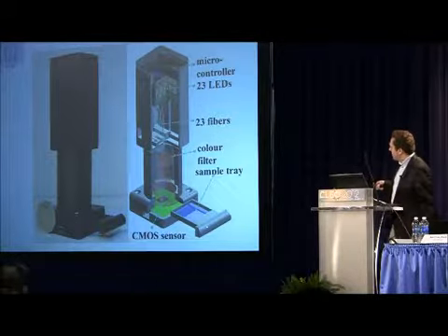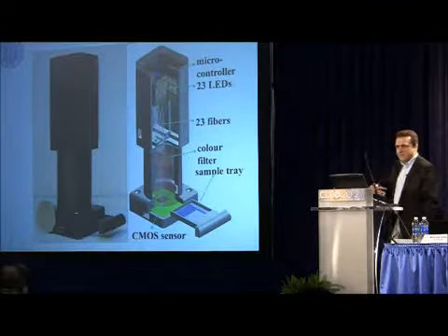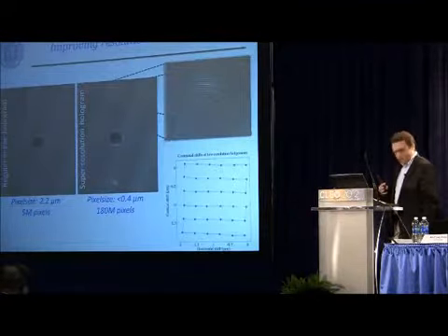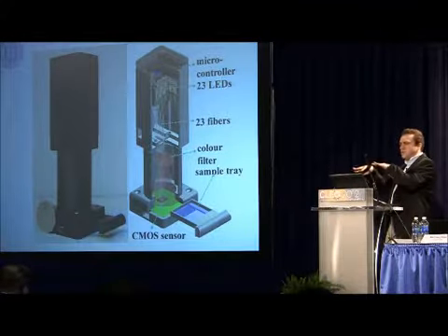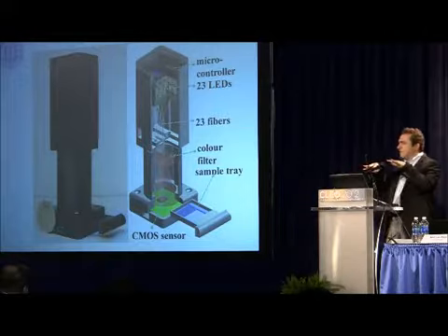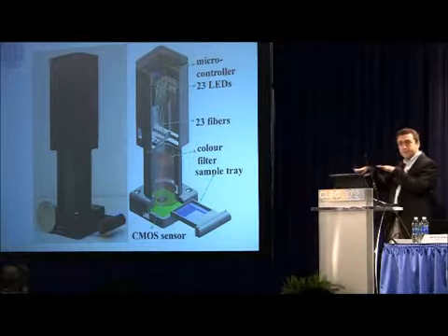And you insert your specimen, which might be a blood smear in this case, for instance, and then you record the lens-free diffraction holograms. What we do is, as a function of time, you just switch on these LEDs one by one, and then the light field or the holographic pattern starts to shift.